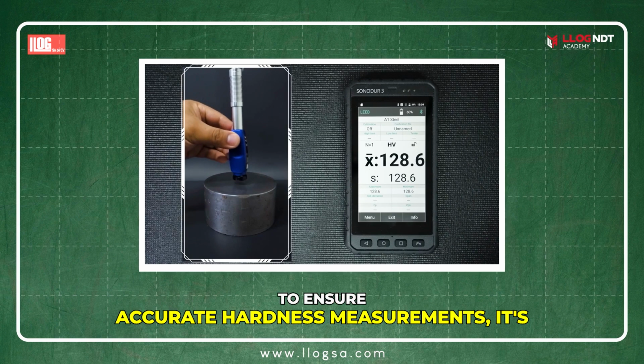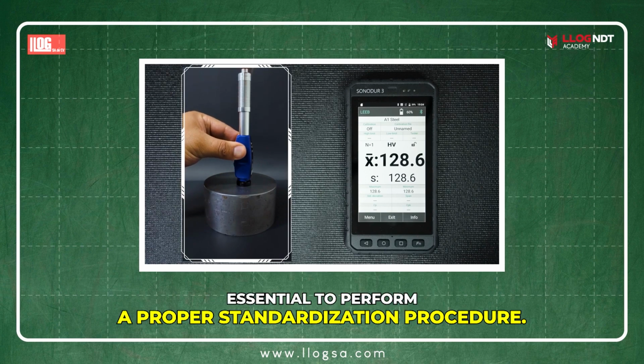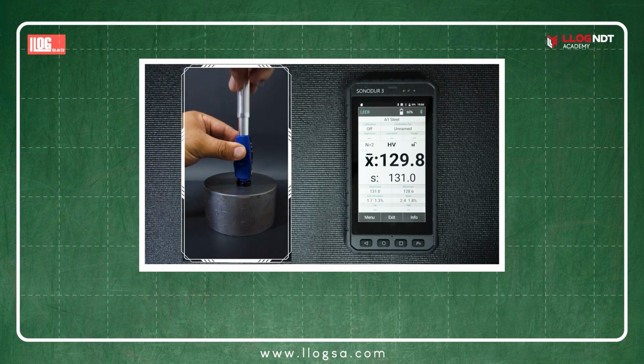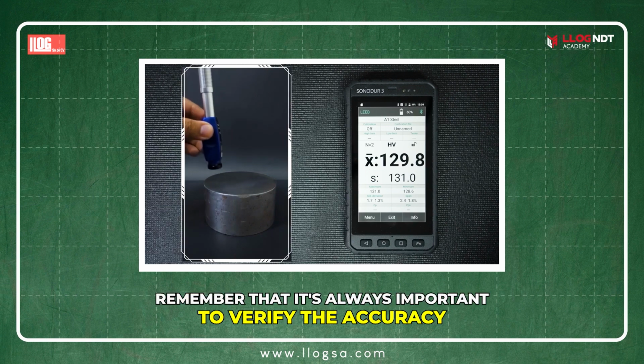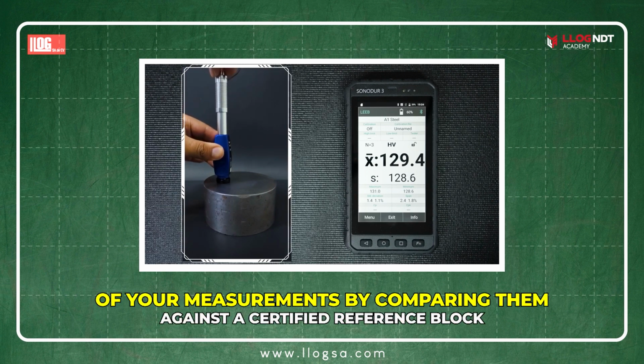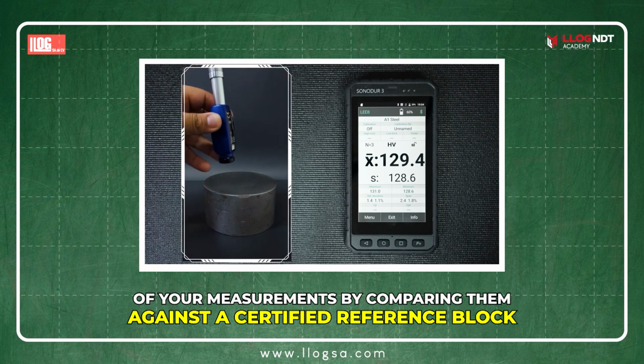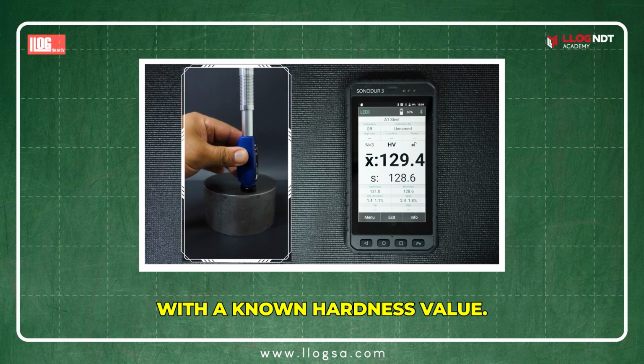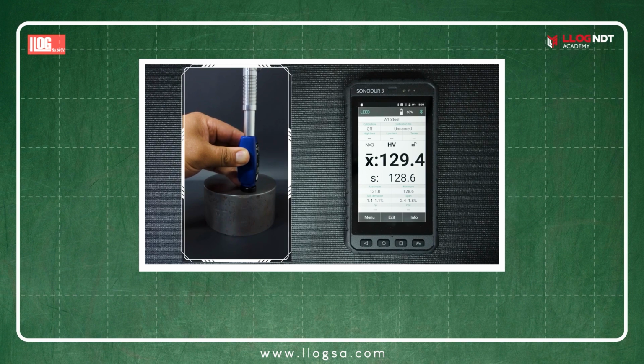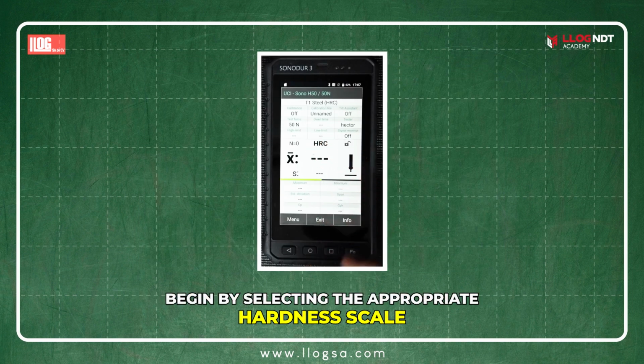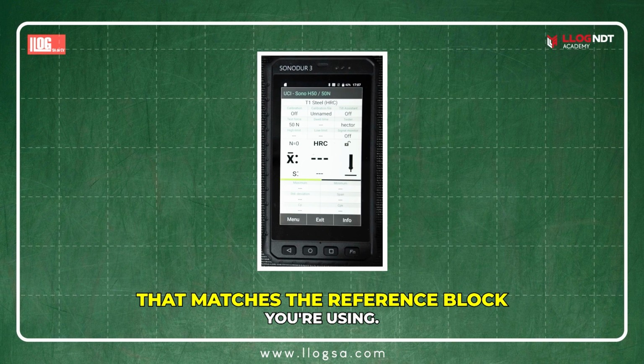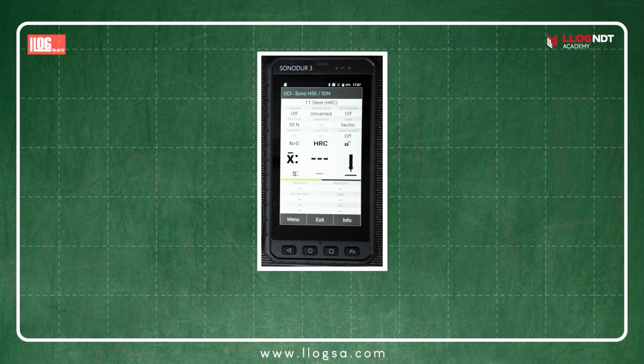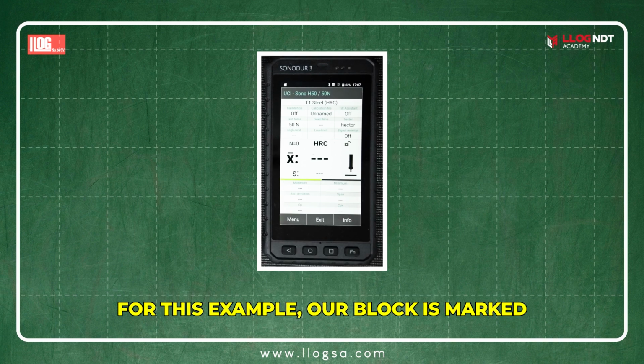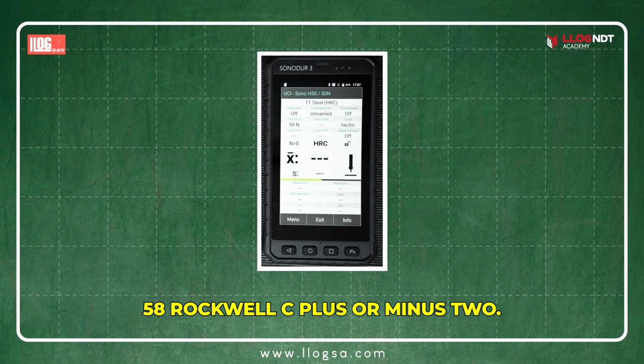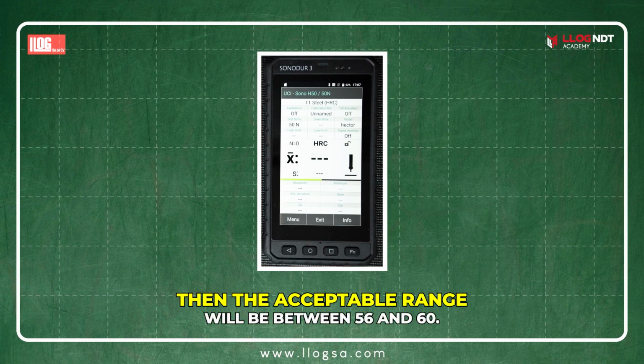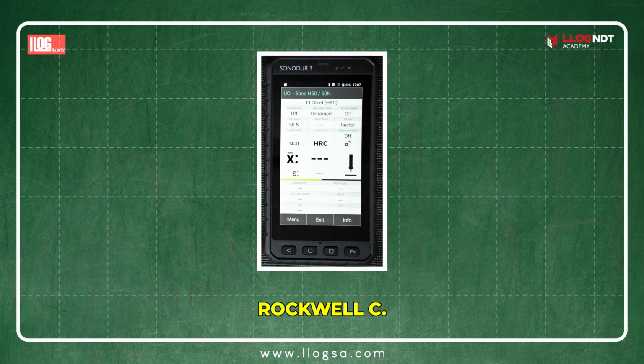To ensure accurate hardness measurements, it's essential to perform a proper standardization procedure. Remember that it's always important to verify the accuracy of your measurements by comparing them against a certified reference block with a known hardness value. Begin by selecting the appropriate hardness scale that matches the reference block you're using. For this example, our block is marked 58 Rockwell C plus or minus 2. Then the acceptable range will be between 56 and 60 Rockwell C.